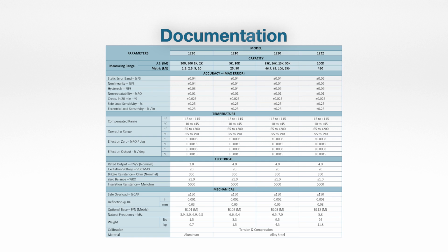Max excitation, that's also a good one to pick up on the data sheet, and also kind of what to expect as far as the zero balance goes. We're going to talk a little bit later about why that may be important to note. Other parameters such as safe overload, standard product is usually for 150% of capacity. That's something you need to make sure is appropriate for your application as well. And then there's connector information for the standard model, and also what cal data to expect. TNC is going to mean you're going to get both tension and compression cal data for that unit.